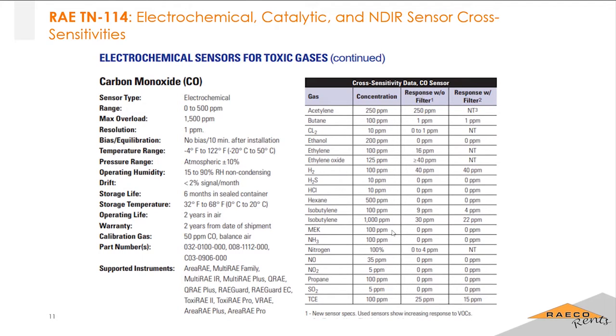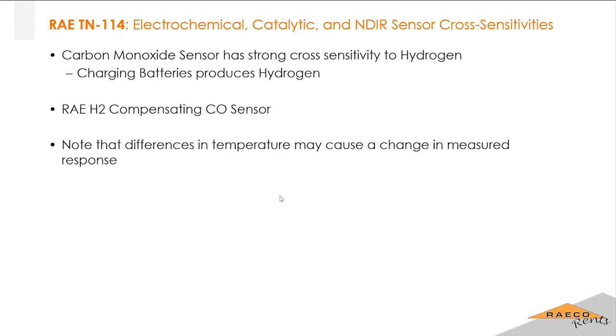There's a lot listed here, but the main one is isobutylene, which is what people use to calibrate PIDs. So if you used a multi-gas monitor with a PID sensor and carbon monoxide, you'd see the carbon monoxide reading jump up if you ran isobutylene across the sensor. If you want to measure carbon monoxide, you've got to make sure you don't have these cross-sensitive compounds in the area. Just something to think about and keep in the back of your head.